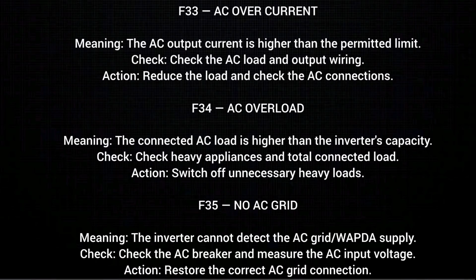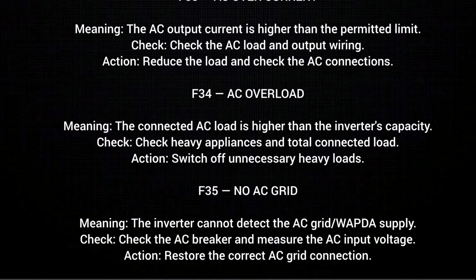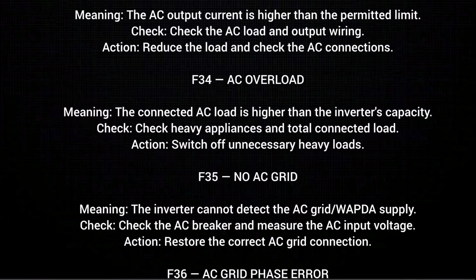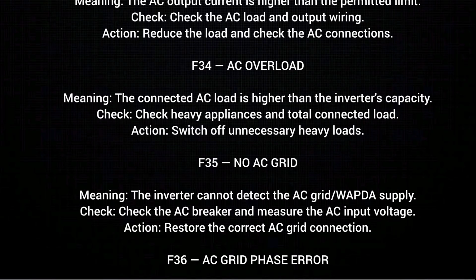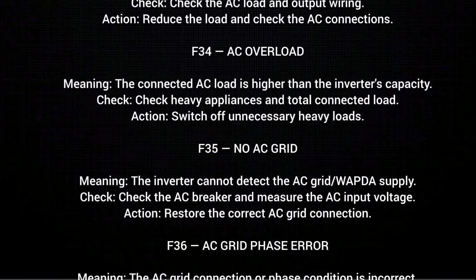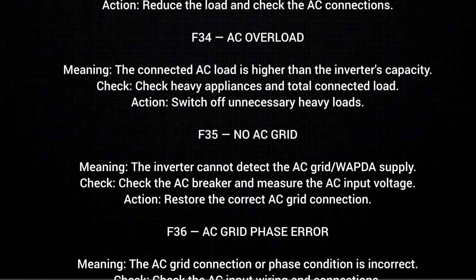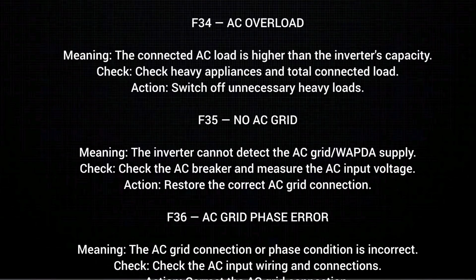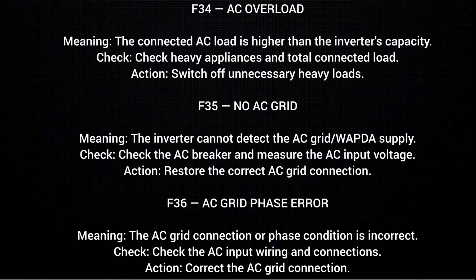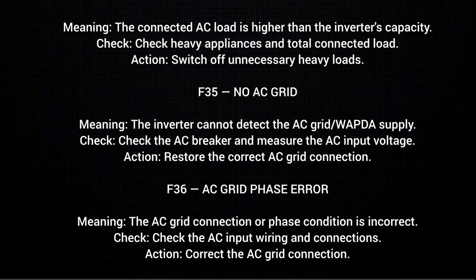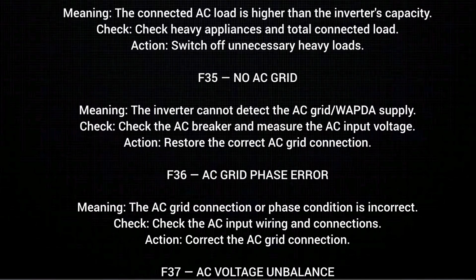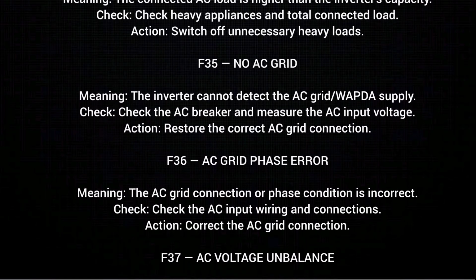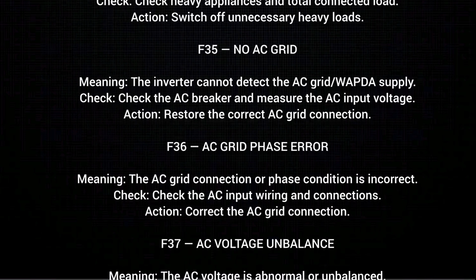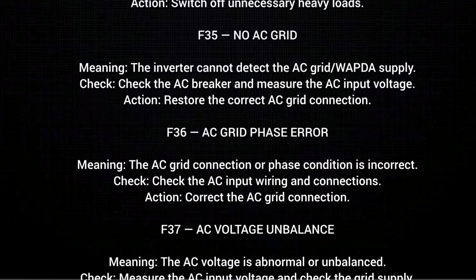F34. AC overload, meaning the connected AC load is higher than the inverter's capacity. Check. Check heavy appliances and total connected load. Action. Switch off unnecessary heavy loads. F35. No AC grid, meaning the inverter cannot detect the AC grid/WAPDA supply. Check. Check the AC breaker and measure the AC input voltage. Action. Restore the correct AC grid connection.